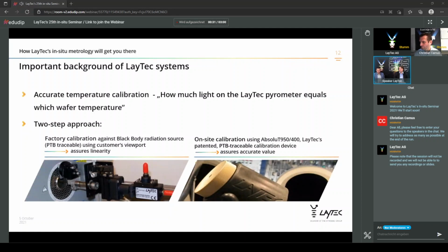In the old days, sometimes still used, is the eutectic calibration, but since many years now, we recommend to use LayTec's calibration tool. This is the AbsoluT, available for both kinds of pyrometers, the IR pyrometer family, EpiCurve, EpiTT. There it is the AbsoluT 950, or on the other hand, the UV pyrometer, the P400. This requires an AbsoluT 400 because you need to calibrate it for the correct wavelength.